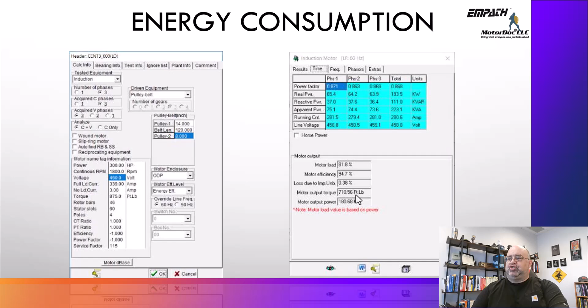So incoming power right there at the connection — this is the shaft power. That incoming power, 193.5 kilowatts, times $10 times 12 months, that is $23,000 in demand. If I look at that in usage: 193.5 times 10 cents per kilowatt hour times 6,000 hours — this is the maximum, the peak load — comes to 116,000. So close to $140,000 per year to run that electric machine, that 300 horsepower, at that particular load.